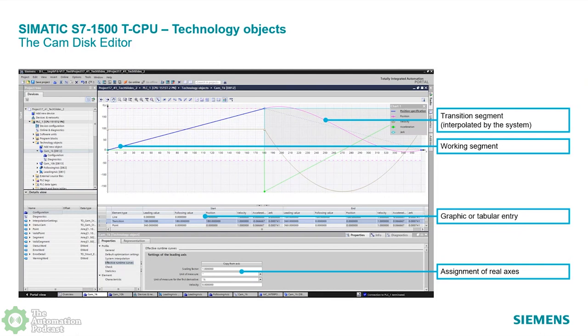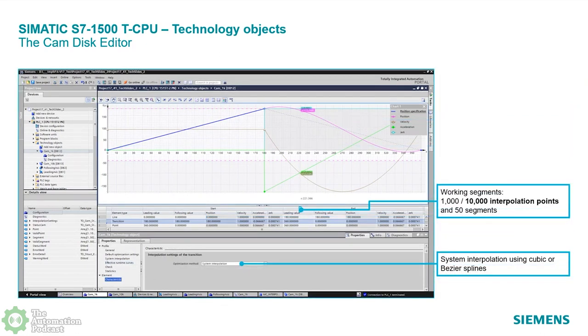A lot of people are blown away that we're trying to make it more user-friendly and prevent the machine from ripping and tearing. Engineers used to design a cam profile going easy first and then building up, which takes a lot of time — wondering when you'll reach the limit. With TIA Portal assigning the real axes with mechanical limits, it tells you right here if it's too aggressive and the drive cannot do it, without you having to actually test it out. There's also more capability to define transitions between line segments — what type of interpolation or optimization you want. The simplest is linear, but there's cubic spline to make it easier on your mechanics so they last longer.